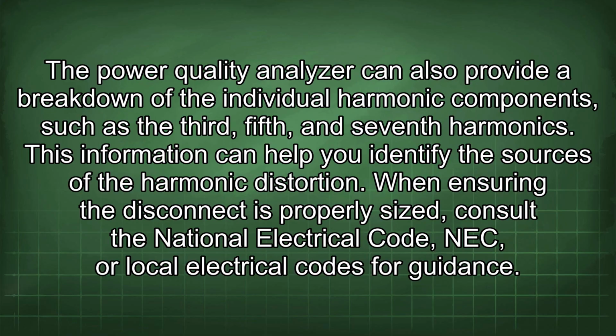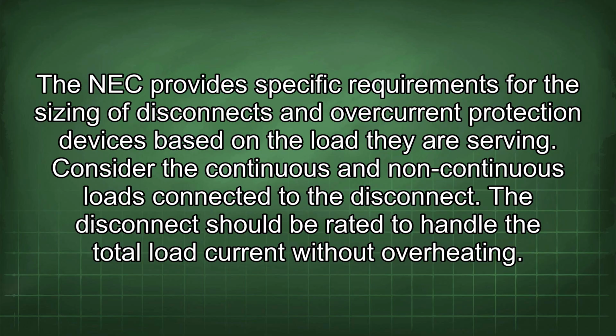When ensuring the disconnect is properly sized, consult the National Electrical Code, NEC, or local electrical codes for guidance. The NEC provides specific requirements for the sizing of disconnects and overcurrent protection devices based on the load they are serving. Consider the continuous and non-continuous loads connected to the disconnect. The disconnect should be rated to handle the total load current without overheating.